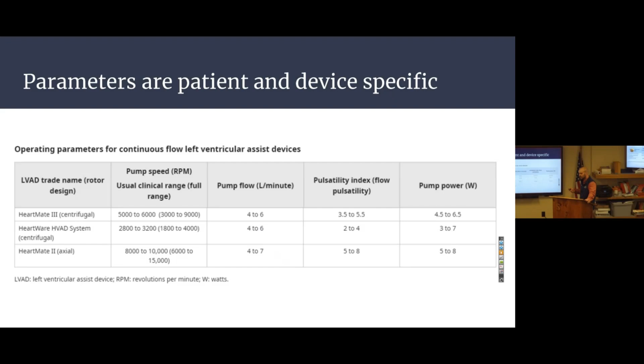Flow is usually 4 to 6, right? That makes sense, right? That's our normal cardiac output. It's about 3 to 5. So it's going to be around there. Pulsatility index and pump power, again, vary depending on machine, but the one that'll vary the most is your pump speed. And they're also patient specific. So they give the patient, like, these are where your numbers should be. So kind of how every patient tells you, like, oh, my blood pressure is always low, or my heart rate's always 50.